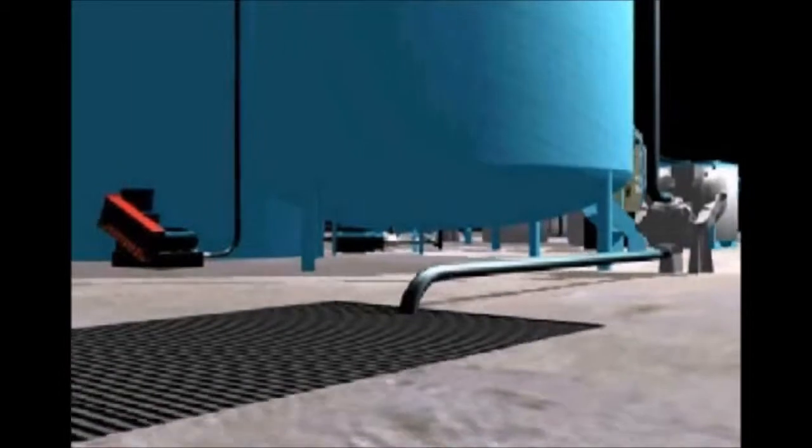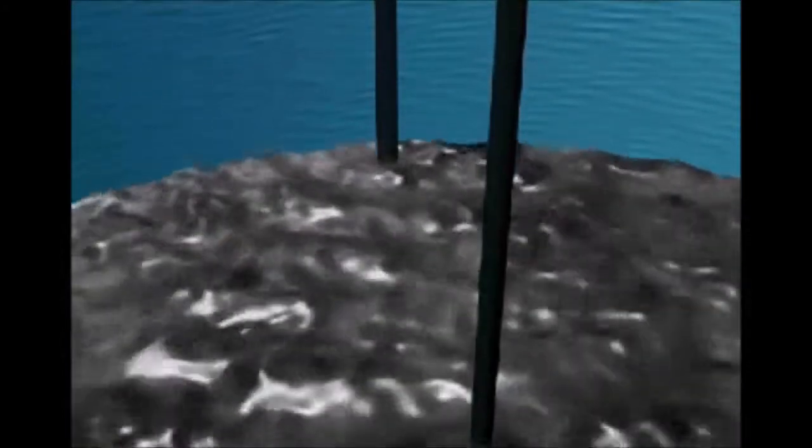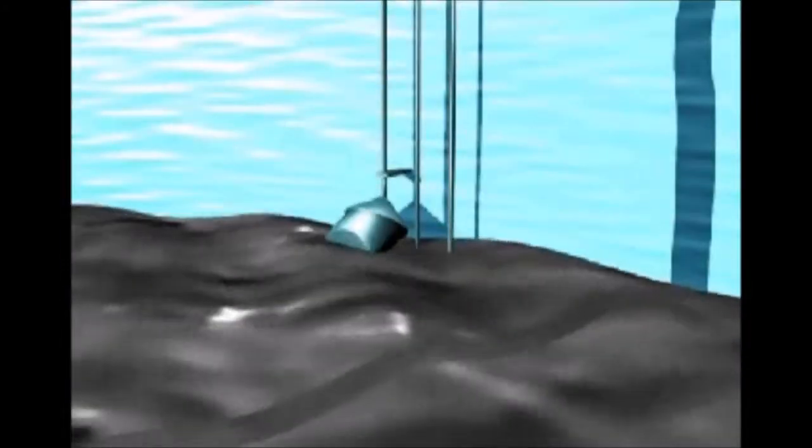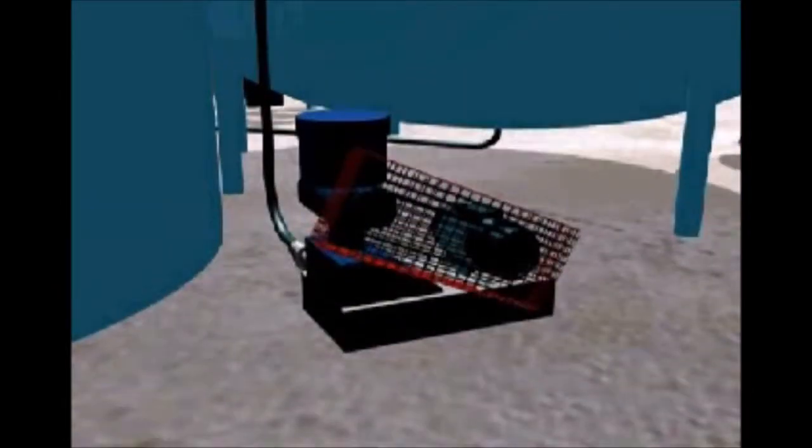Wastewater generated in the plant flows through collection trenches and receiving pits, from where it is pumped to a collection tank called the equalization tank. The equalization tank is equipped with float level sensors that control the transfer pump to the treatment tank. To maintain the equalization tank homogeneous, an air sparge is used. Air generated by the blower, which eliminates dependence on compressed air, keeps the tank agitated and avoids settling out of solids and anaerobic decomposition of the wastewater.